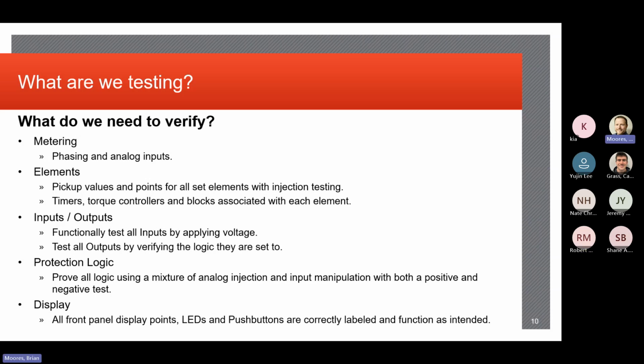So you've got inputs into the relay: logical, digital inputs, and analog inputs, which are your voltages and your currents. For the most part, it's really looking at voltages and currents, because that's how it's seeing the power system element that it's protecting. It monitors those via CTs and PTs or CCVTs, some sort of voltage transformer or current transformer, to transform it down to a usable signal. It looks for an abnormal condition, and digital inputs could help drive some of those decisions as well.